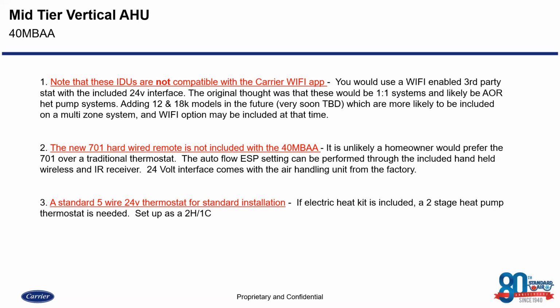So W1 is a call for heat, Y1 is the call for cooling. Now, if we have electric heat, we can set that up as a 2 heat, 1 cool option. Same thing, W1 is the call for the ductless heat pump, Y1 is the other call for cooling for the ductless heat pump, and then W2, when set up in this configuration, will tell the unit to be able to kick on those strip heaters depending on when you want to set that threshold on how low that temperature drops before that electric heat kicks on.